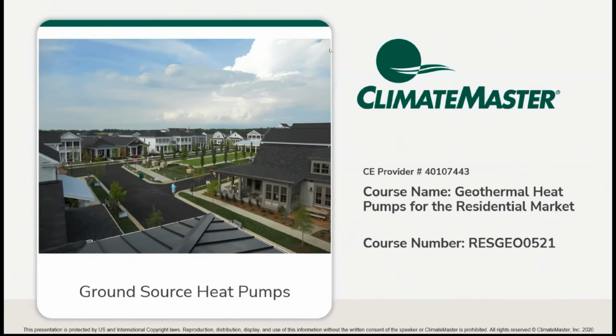I have cold spots in my house. Will this new system make them go away? In a word, no. We have the same air distribution system as your existing unit does. The only thing that may make that a little more palatable is a multi-stage unit that runs a little bit longer, therefore heating or space conditioning all areas of the house a little bit longer.